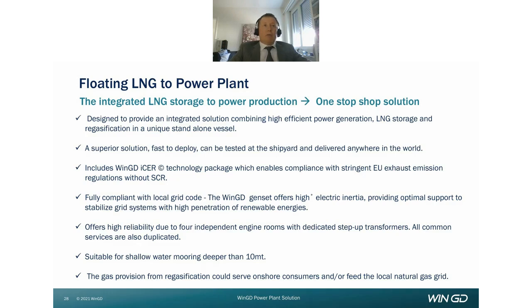The floating storage power unit, in summary, provides the following value proposition. It's fully tested as a system at the shipyard, so it is fast to be deployed and delivered anywhere in the world. It complies with stringent EU emission standards without the usage of any urea. It fully complies with the local grid code. The WinGD genset offers high electric inertia, providing optimal support to stabilize grid systems with high penetration of renewable energy.